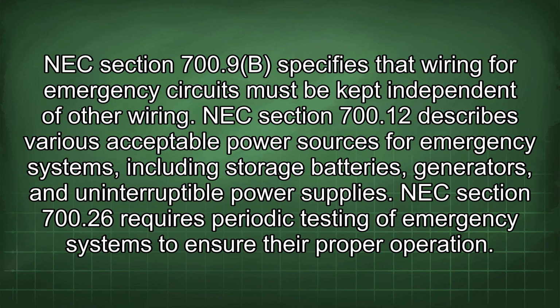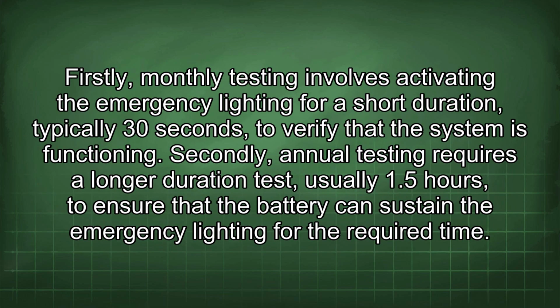NEC Section 700.26 requires periodic testing of emergency systems to ensure their proper operation. Firstly, monthly testing involves activating the emergency lighting for a short duration, typically 30 seconds, to verify that the system is functioning. Secondly, annual testing requires a longer duration test, usually 1.5 hours, to ensure that the battery can sustain the emergency lighting for the required time.